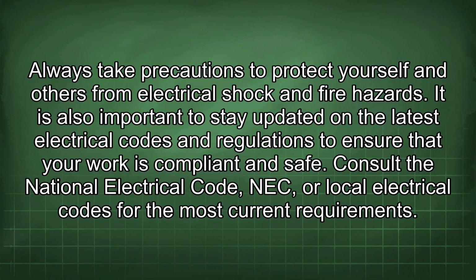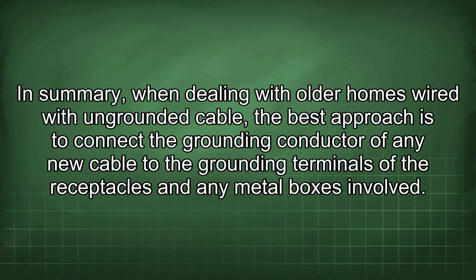It is also important to stay updated on the latest electrical codes and regulations to ensure that your work is compliant and safe. Consult the National Electrical Code, NEC, or local electrical codes for the most current requirements. In summary, when dealing with older homes wired with an ungrounded cable, the best approach is to connect the grounding conductor of any new cable to the grounding terminals of the receptacles and any metal boxes involved.